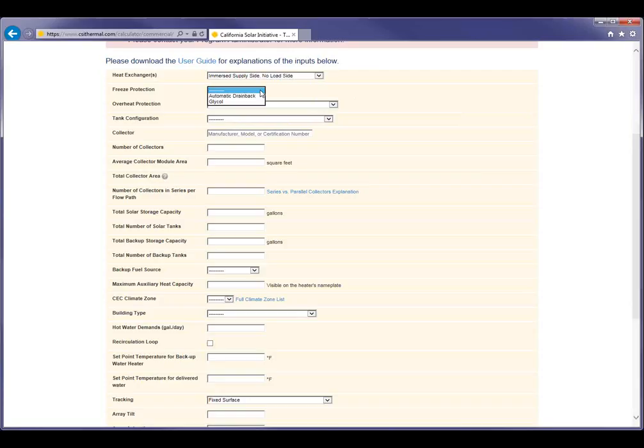The freeze protection is typically achieved either through what we refer to as an automatic drain back, where the collector loop pump shuts off, and all of the piping from the roof is sloped back to a drain back tank, which is placed within the building envelope, either in an attic or a garage. Doesn't necessarily have to be conditioned space, but within the building envelope. And that essentially removes all of that fluid from the exposed piping and collectors on the roof to prevent freezing. And then when the temperature sensors sense that there's a temperature rise across those collectors, the pump will reactivate and circulate collector fluid, generating heat again from solar. And so that effectively prevents freezing.